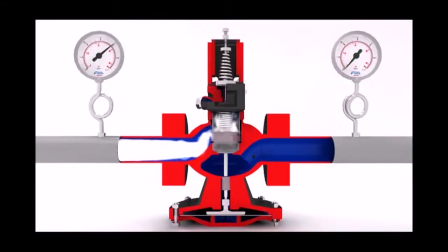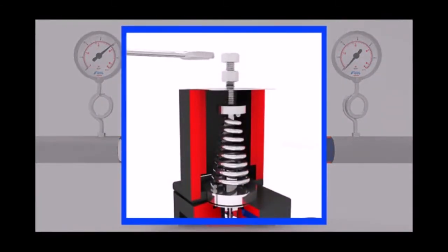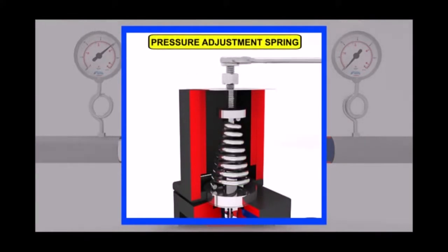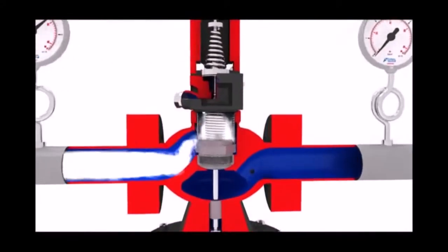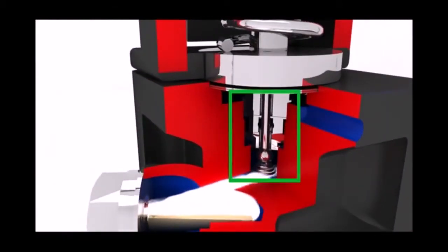And steam remains accumulated in the main valve chamber. Tightening the pressure adjustment bolt compresses the pressure adjustment spring. This results in deformation of the pilot diaphragms, which in turn pushes the pilot valve plunger and SS ball against the spring located below, causing the pilot valve to open.